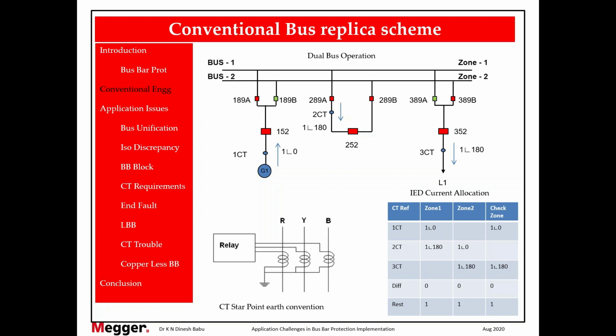It is flowing away, therefore 180. So one side is 0, one side is 180, it's flowing here. Now you can see what the differential current is. 1 angle 0 plus 1 angle 180, differential current 0. Here also 0 plus 180, differential current 0. Now check zone. Bus coupler is not in the picture. Incoming current, outgoing current, so this is also 0. So the system is perfectly balanced.